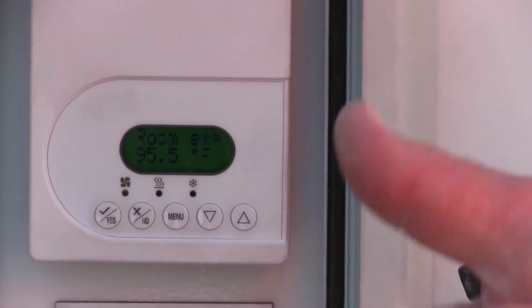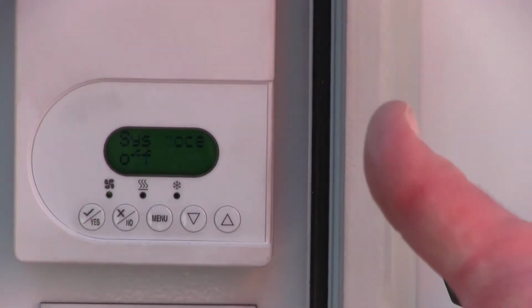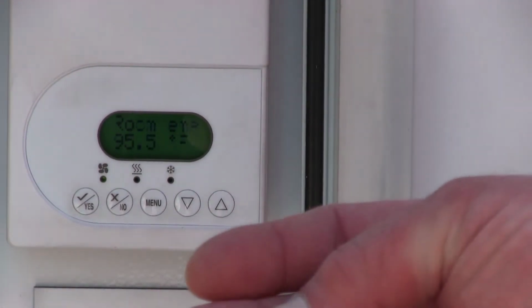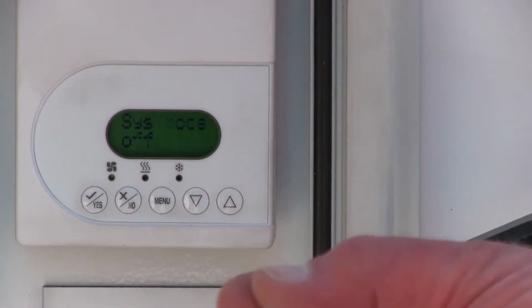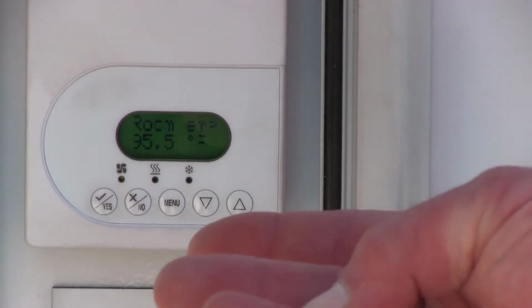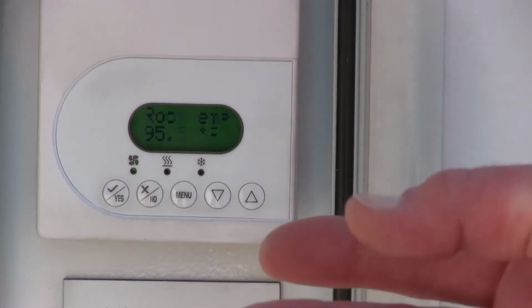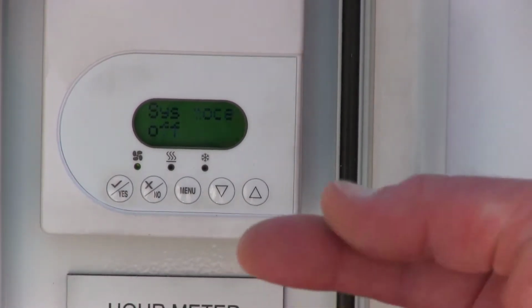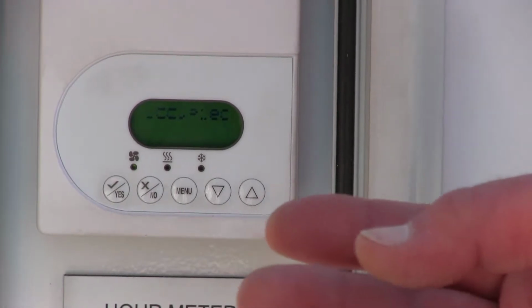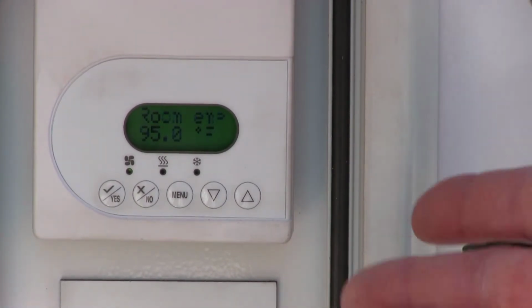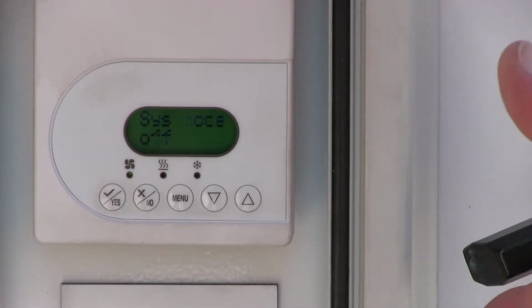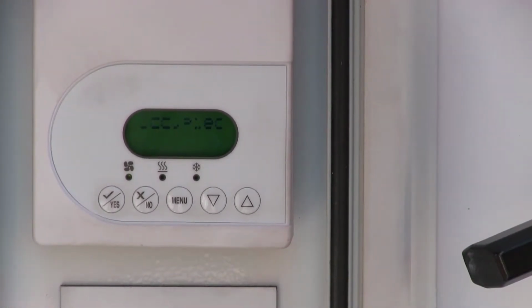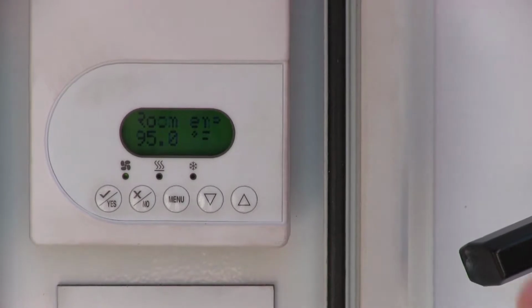So the first thing you want to know is that these thermostats are capable of 4 modes. The first one is off, the second is cooling, the third is heating, and the fourth is auto. Now, depending on your job specifications, you may only have enough power to run cooling. You only want to set it in cooling, or in heating, it requires more power, and certainly in dehumidification requires the most power. So you'll want to determine what mode based on how much power you have and based on the job specifics.